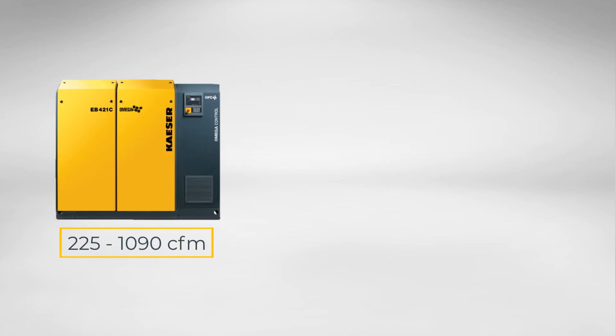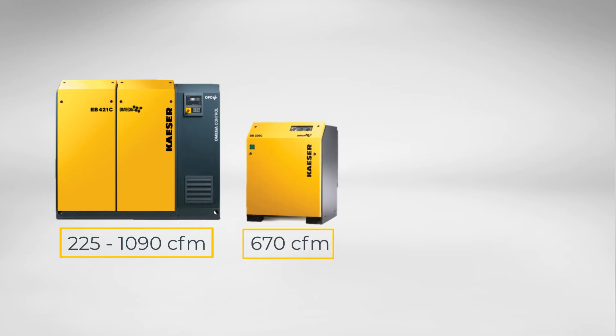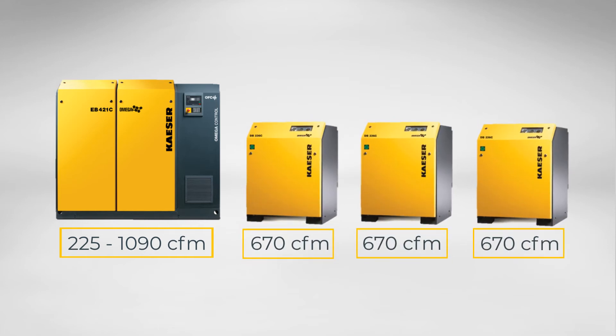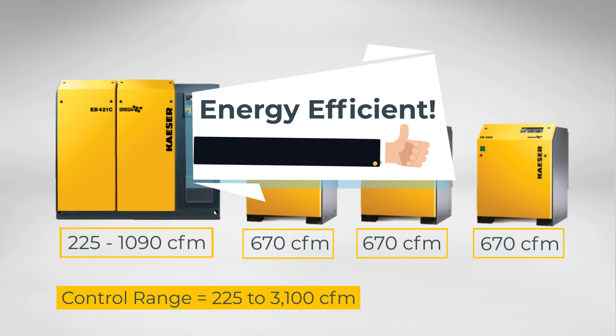Select units that have as flat a performance curve over varying speeds as possible. And to prevent control gap, size VFDs with a control range that exceeds the flow of the fixed speed blowers. While the VFD will likely run much of the time, the fixed speed machines should be the workhorses of the system, with the VFDs smoothing out the small variations in demand. Properly sized machines can be placed in a short idle or standby state for rapid response to varying demands. A machine in idle will use far less energy than a loaded machine venting unneeded air, and will use no energy when turned off.